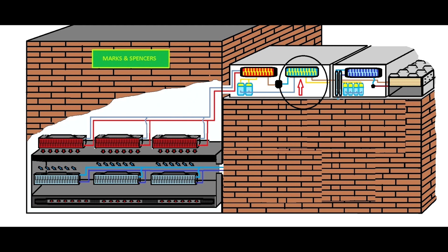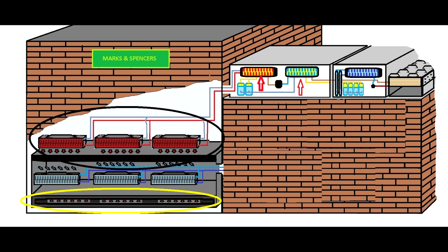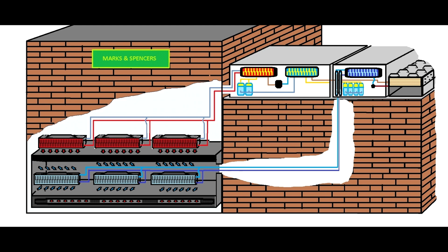The first one is the water which circulates to heat the heat exchanger in the store - the red one. The second one is another heat exchanger which heats the refrigerant 410A. And the third one is the heat exchanger which goes straight into this carbon dioxide subcritical system, which is used as a liquid to cool down the heat exchanger that cools the product. So the heat comes in from the top and comes out from the bottom - the recovered heat.